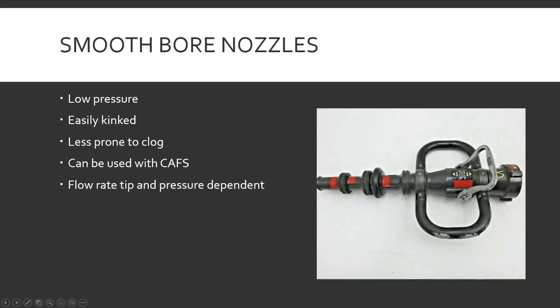Flow rate on smoothbore nozzles is tip and pressure dependent. Different tips — inch-and-three-quarter, inch-and-a-half, inch size — can be stacked. The more tips you stack on, you may get more reach but may get less volume because you're forcing water out of a smaller hole. And pressure dependent — obviously the more pressure you put behind it, the more reach and flow you can probably get.